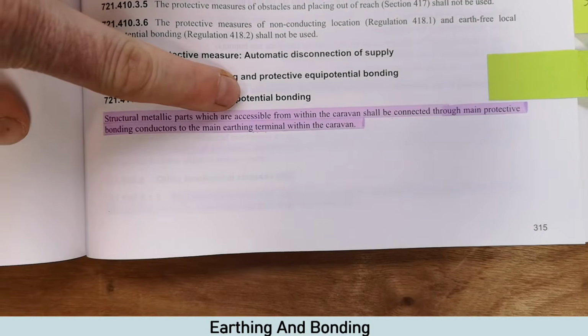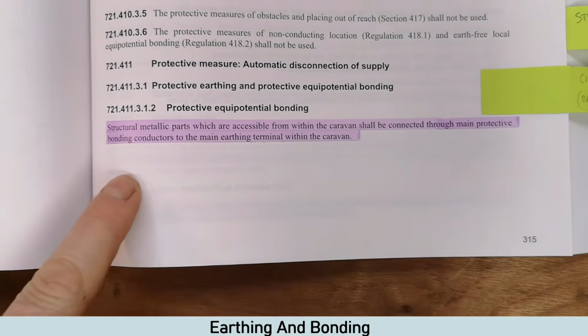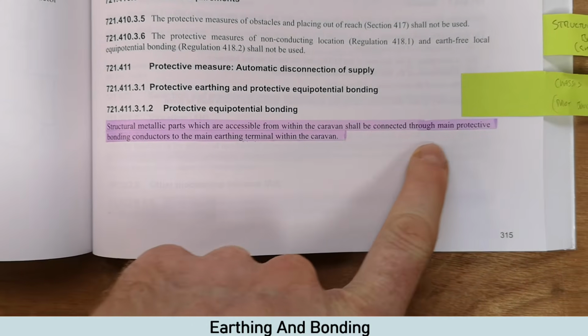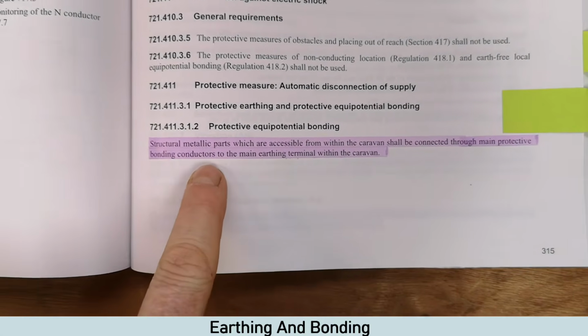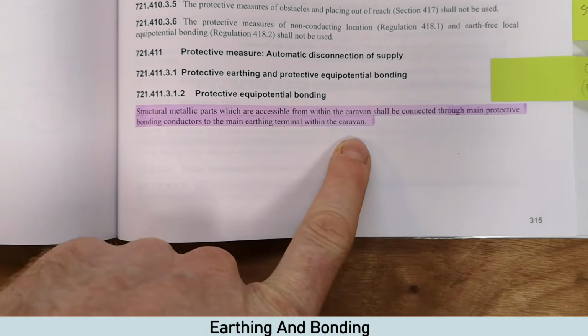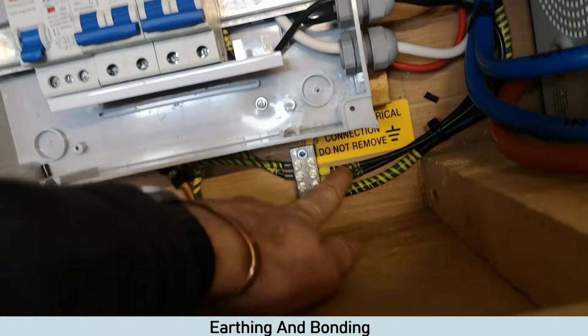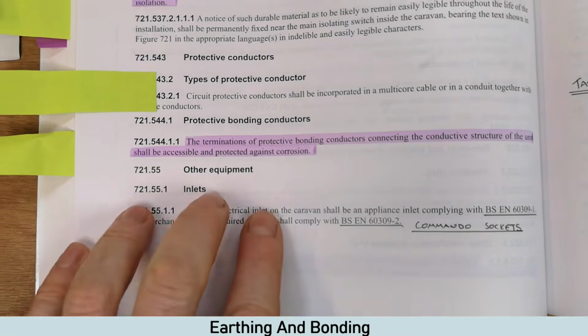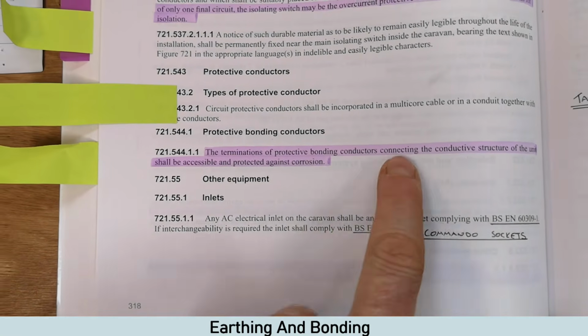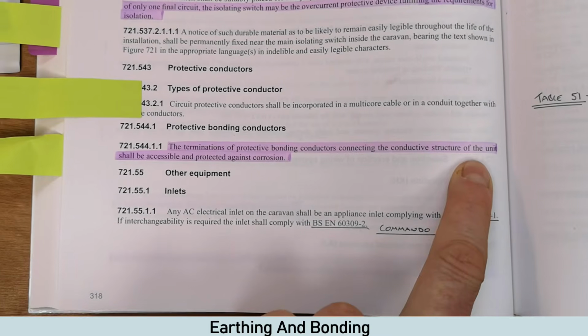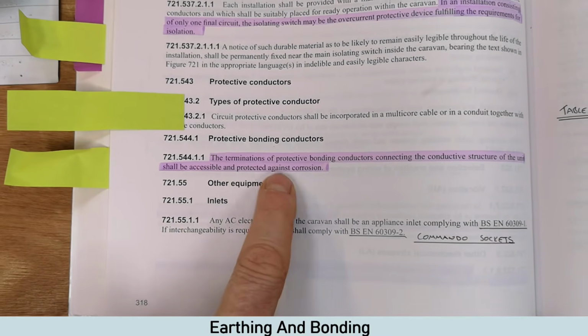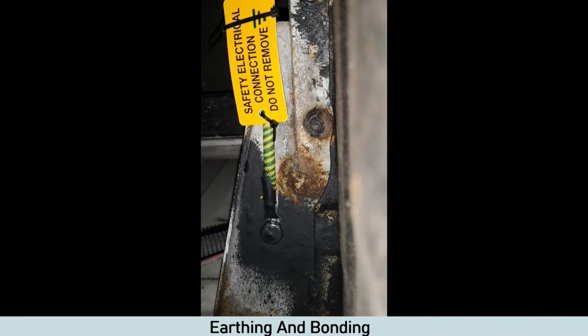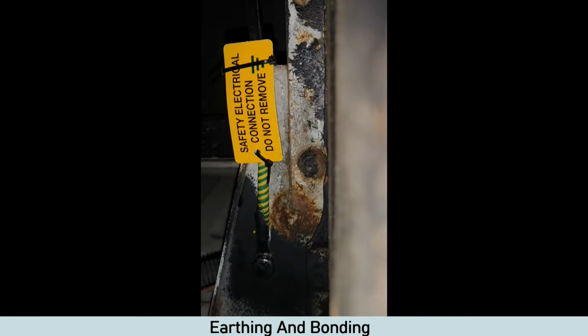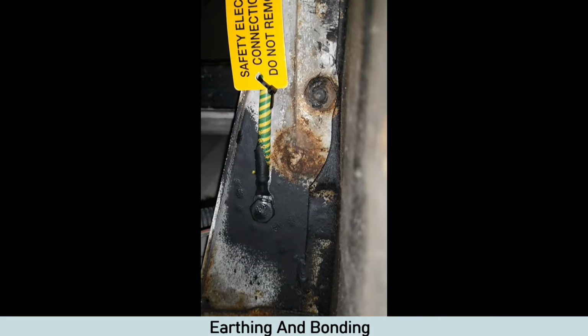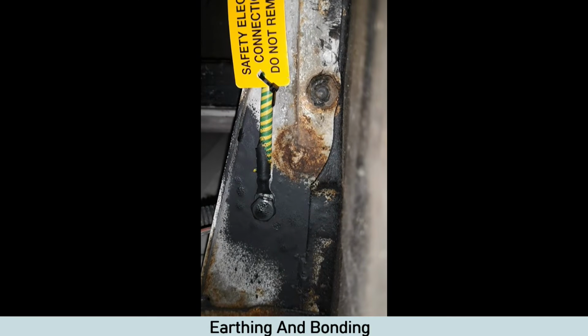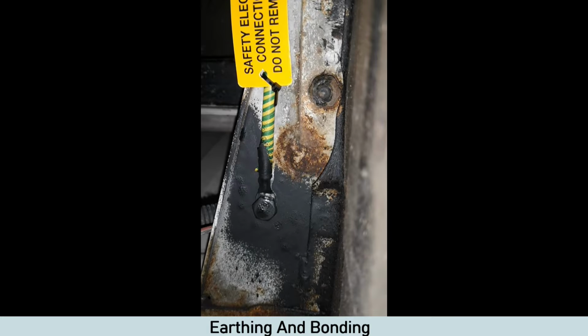Protective equipotential bonding. It says the structural metal parts which are accessible from within the caravan shall be connected through main protective bonding conductors, that's the cable, to the main earth terminal within the caravan. So that's your chassis bond, this one here. Another note on the chassis bond: the regs state that termination of the protective bonding conductor connecting the conductive structure of the unit, so the chassis, shall be accessible and protected against corrosion. Just to show you, this is the chassis connection. It's got a safety electrical connection, do not remove label, and we've taken it back to bare metal, put the connection on, and then put some rust protection spray on to stop it corroding.